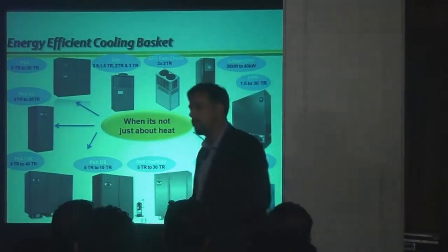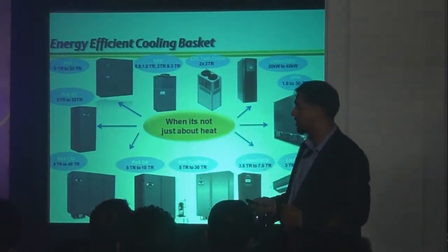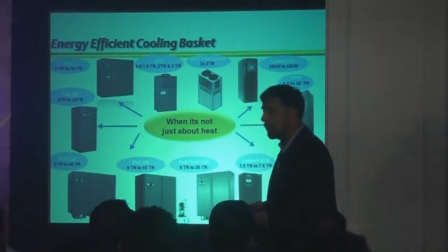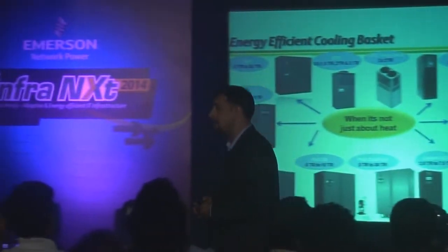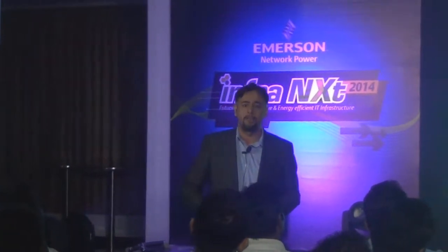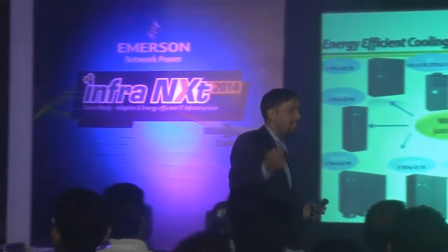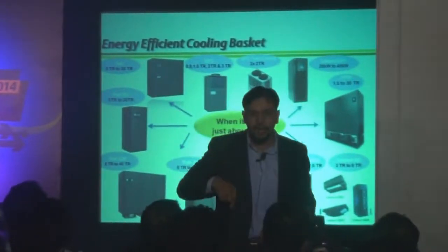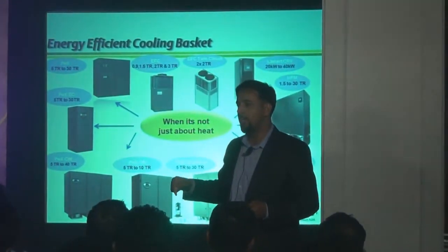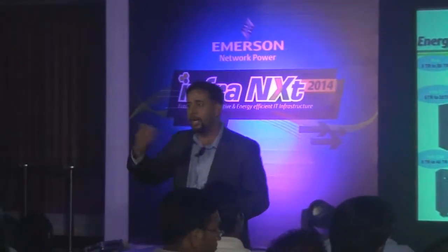Emerson has various cooling solutions. As I said, we cater to many of the applications in the market. On the telecom side, we have smaller units of free cooling type which are available in 2TR, 3TR or 4TR, which are basically for the shelter application. Whenever the outside temperature in the shelter is low, we can utilize the outside ambient to cool the indoor heat. At that point of time the compressor does not work, only the fan is working to circulate the air outside. Then whenever the outside ambient temperature increases, the compressor starts functioning and provides the cooling. Okay, so it's a free cooling with emergency cooling.